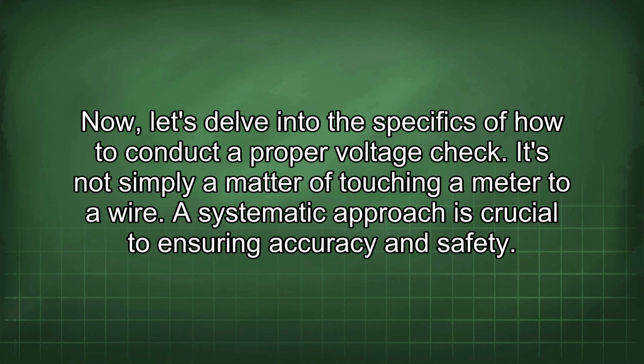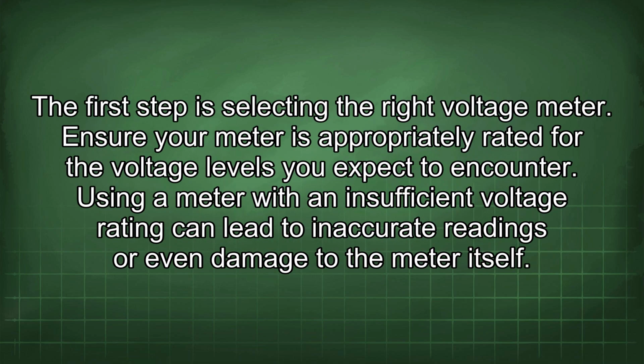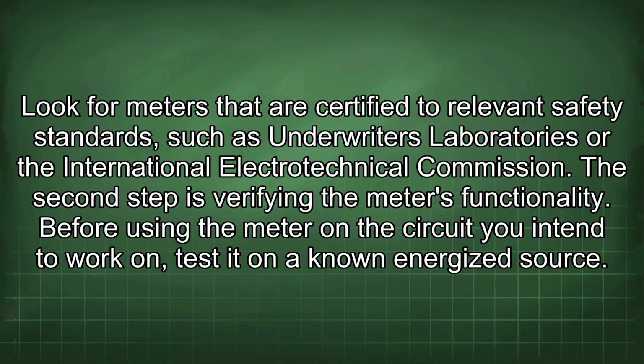Now let's delve into the specifics of how to conduct a proper voltage check. It's not simply a matter of touching a meter to a wire. A systematic approach is crucial to ensuring accuracy and safety. The first step is selecting the right voltage meter. Ensure your meter is appropriately rated for the voltage levels you expect to encounter. Using a meter with an insufficient voltage rating can lead to inaccurate readings or even damage to the meter itself. Look for meters that are certified to relevant safety standards such as Underwriters Laboratories or the International Electrotechnical Commission.